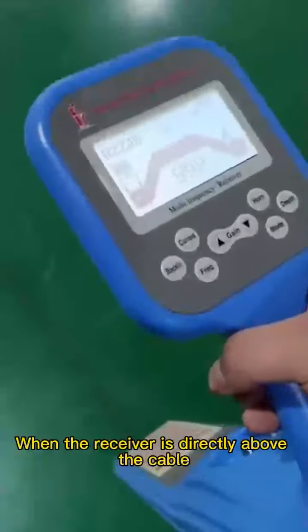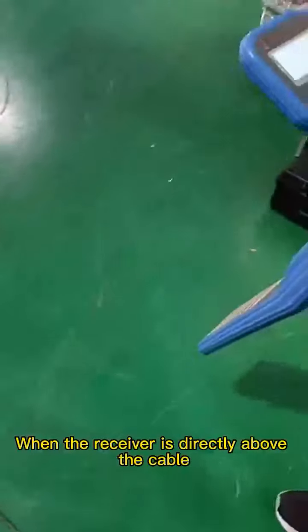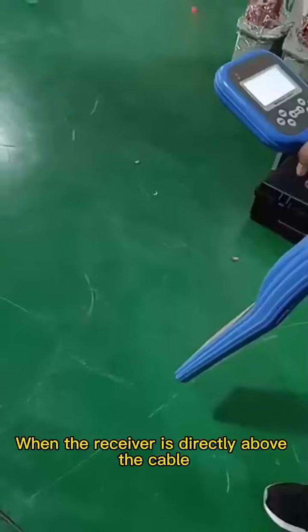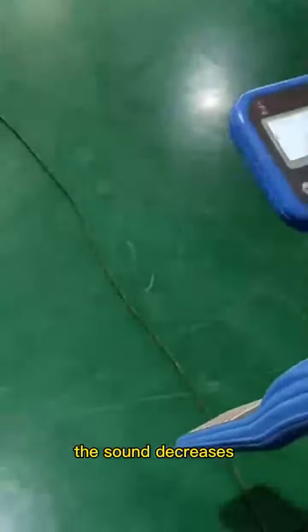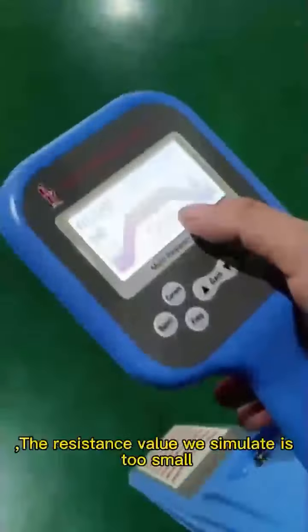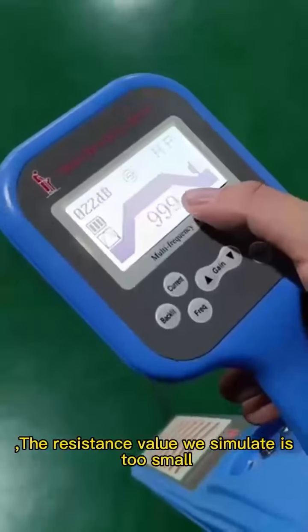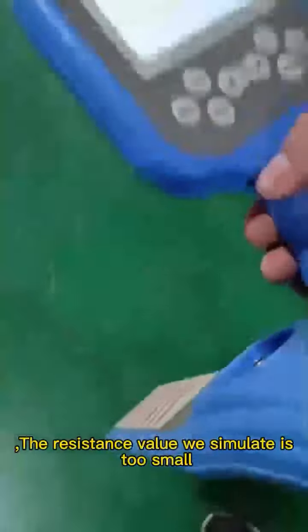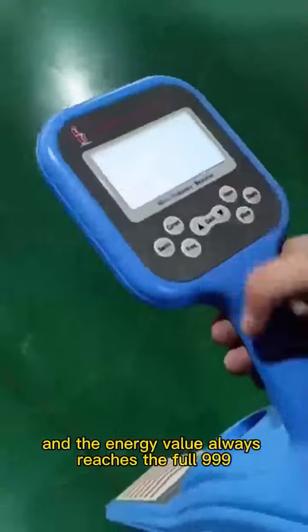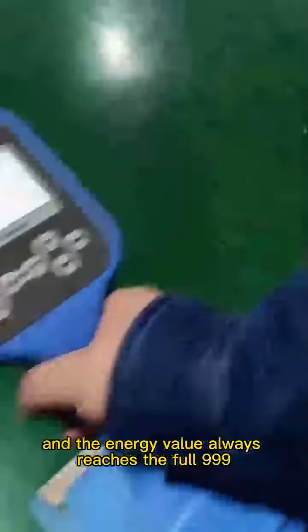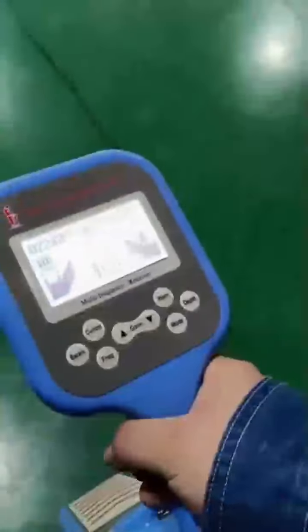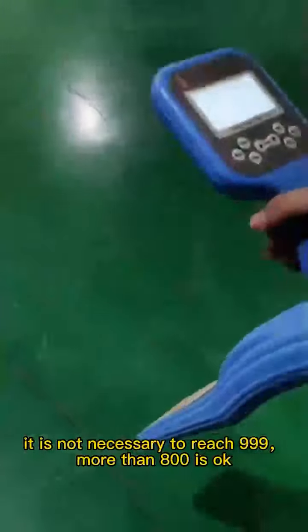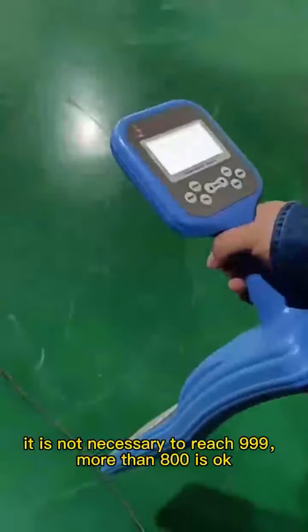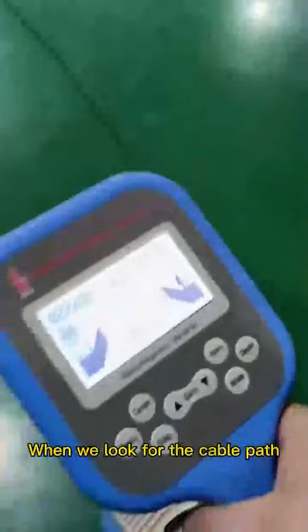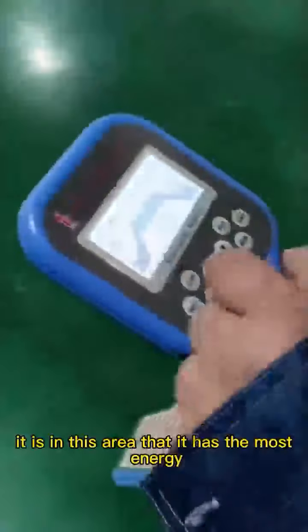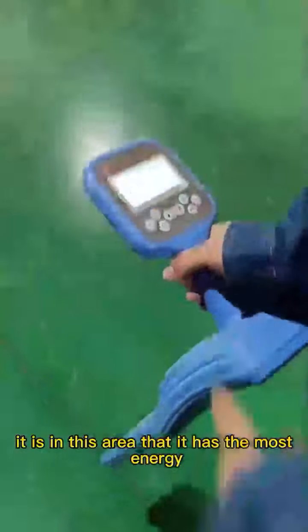When the receiver is directly above the cable, it is loudest, and away from the cable, the sound decreases, indicating a good calibration. The resistance value we simulate is too small, and the energy value always reaches the full 999. Generally, it is not necessary to reach 999. More than 800 is okay. When we look for the cable path, it is in this area that it has the most energy.